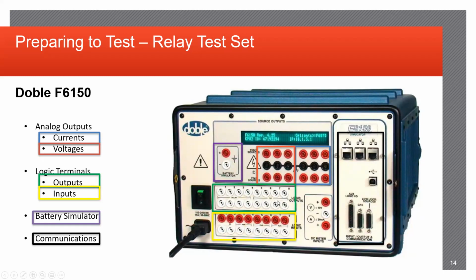So your logic terminals here shown in the green and yellow squares are going to be your outputs and inputs. The outputs are for the test set specifically. So this will usually be connected to the battery simulator here in this purple square, which is a DC source that you can enable from the test set or from the software itself. This will usually be 125, which is standard for most of the relays that you'll be encountering.